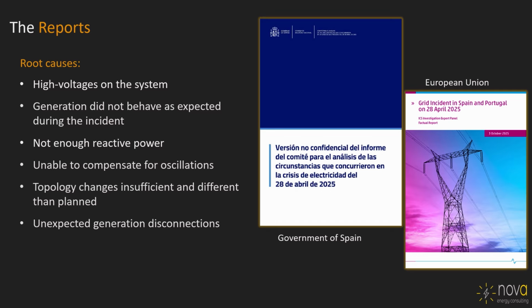What they mentioned in the report primarily is that high voltages were a contributing factor. They also say the generation did not behave as per the rules. When they analyzed how each generator was accelerating and decelerating, moving around that frequency and trying to compensate, they found they did not behave as per the rules agreed with each other. In this Spanish case, there are a bunch of different operators of individual power production networks. So the mechanism to agree, other than at the technical level — being physically connected and the protections coordinated — there's also commercial agreements on how things are supposed to respond in situations like this.